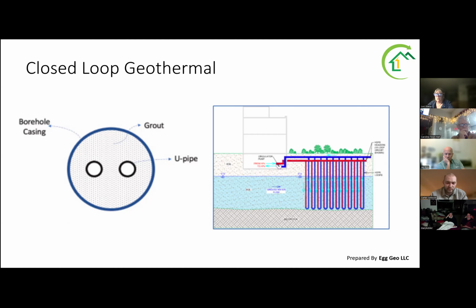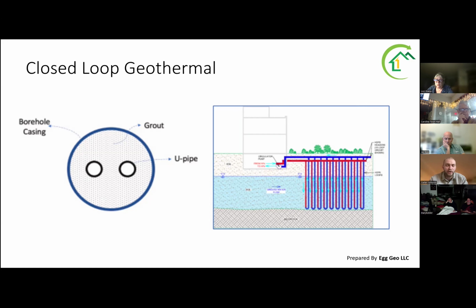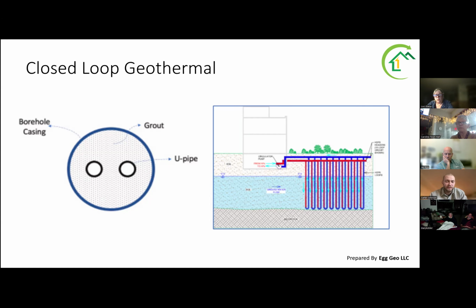With the closed loop system, traditional closed loop is a whole encapsulated system where a working fluid is contained and circulated to harvest heat from the ground. So there's no water leaving or returning to the aquifer. That secondary fluid goes into the ground via a U pipe, the most standard way to do this, though there are other formations it can be done in. Essentially you're mining the stable temperature of the ground; the heat transport fluid runs through the rock and back up to the surface for heating or cooling applications. It's currently the most prevalent design for borehole heat exchangers.